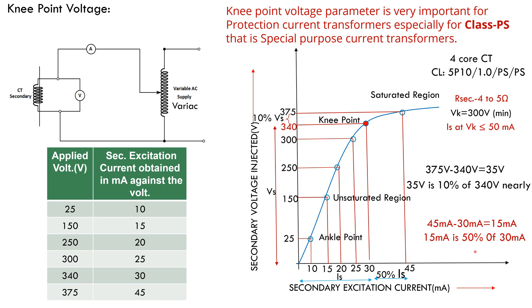This rises from 340 volt to 375 volt. Voltage increases by 10% and current increased from 30 milliamps to 45 milliamps. Current increased by 50%. Hence, the knee point voltage of the given current transformer is 340 volt.